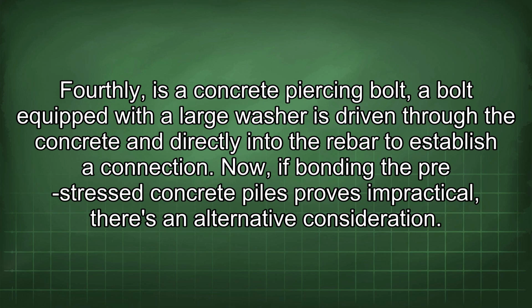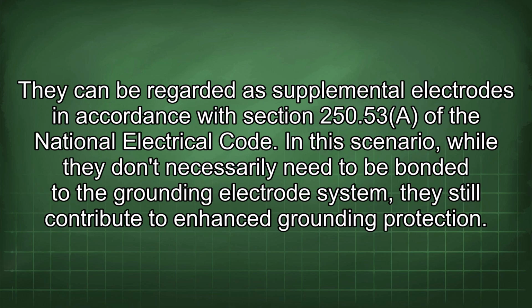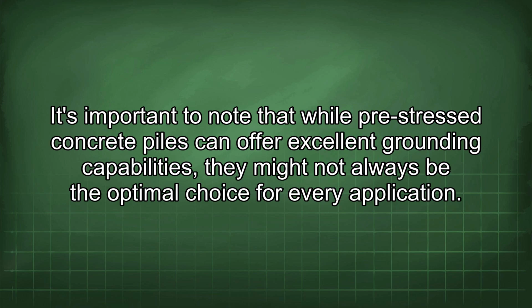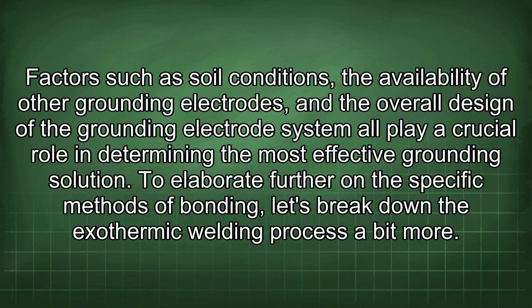Now, if bonding the pre-stressed concrete piles proves impractical, there's an alternative consideration. They can be regarded as supplemental electrodes in accordance with Section 250.53 of the National Electrical Code. In this scenario, while they don't necessarily need to be bonded to the grounding electrode system, they still contribute to enhanced grounding protection. It's important to note that while pre-stressed concrete piles can offer excellent grounding capabilities, they might not always be the optimal choice for every application. Factors such as soil conditions, the availability of other grounding electrodes, and the overall design of the grounding electrode system all play a crucial role in determining the most effective grounding solution.